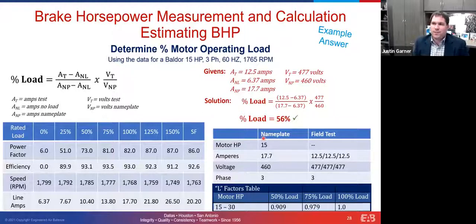But you couldn't pull that 17 and a half horsepower motor out and put it on a pump in the central plant in the same facility and expect it to last at 17 and a half horsepower. So I hope maybe that's where that person was going, but that's the only way that I know you can do it.